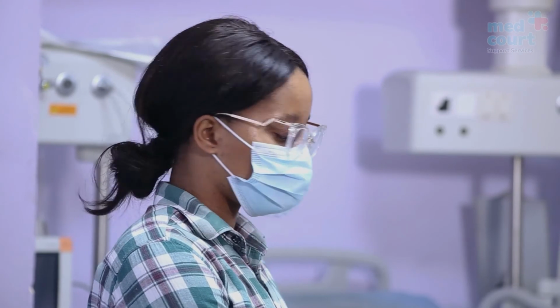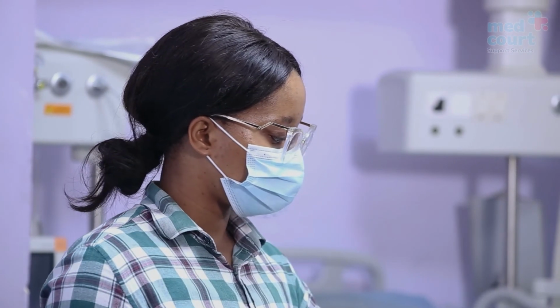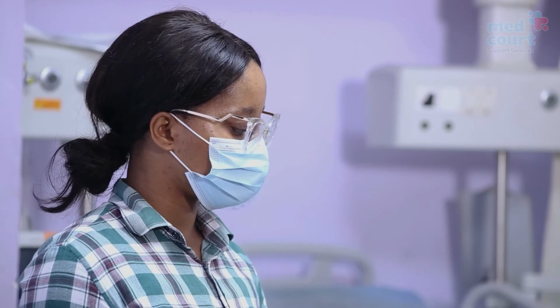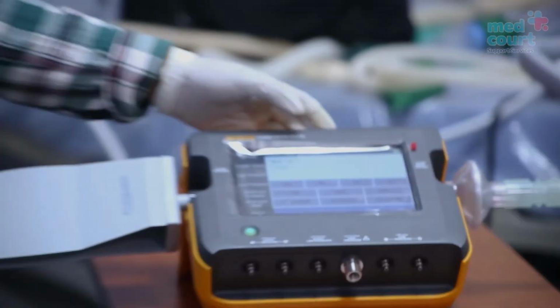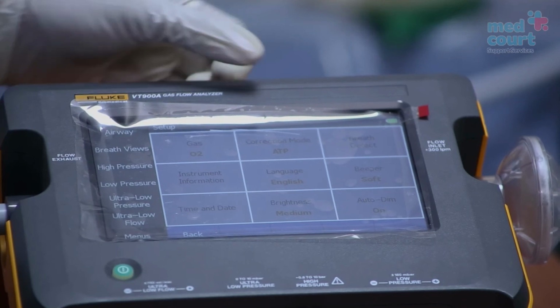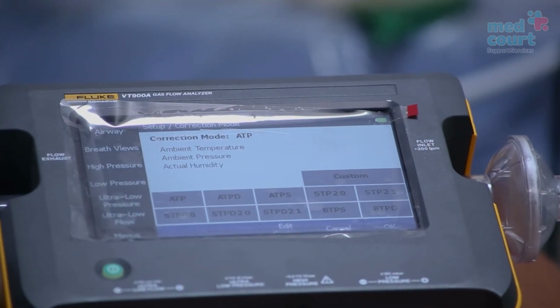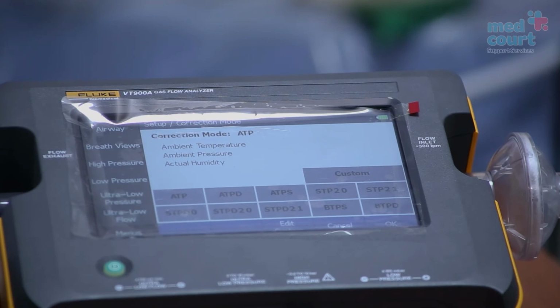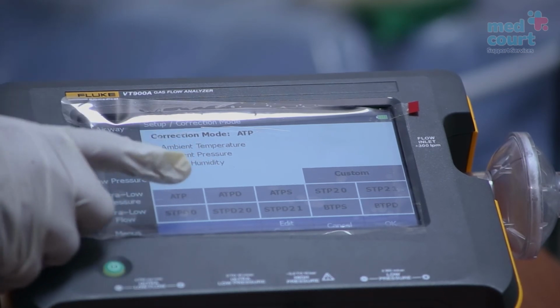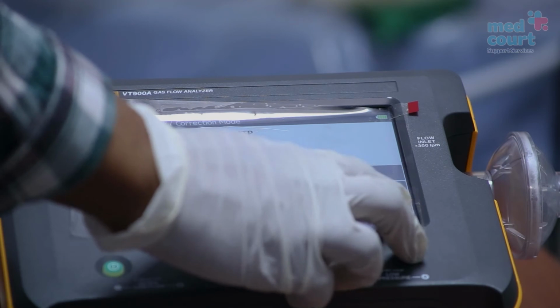There needs to be some setting adjustments on the VT900A. To do this, go to Menus, Setup. Here you can select what gas, correction mode, breath detect mode will be used. For the gas, oxygen is the preferred gas. Select oxygen and click OK. For the correction mode, ambient temperature and ambient pressure will be used. Click on ATP and press OK.